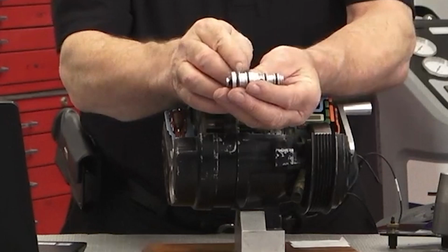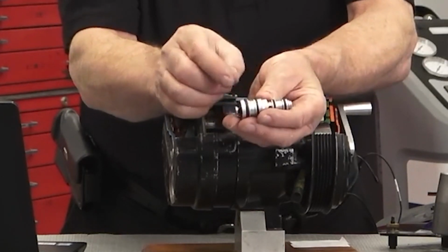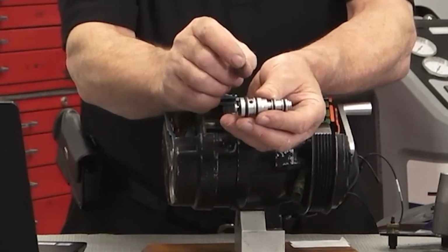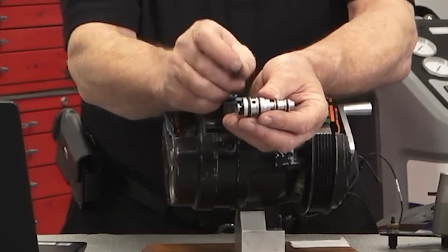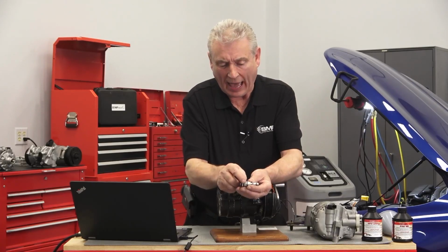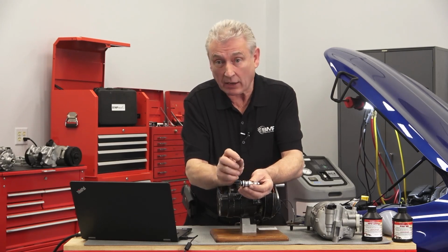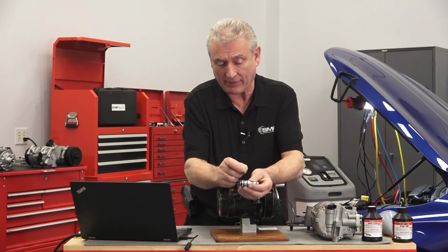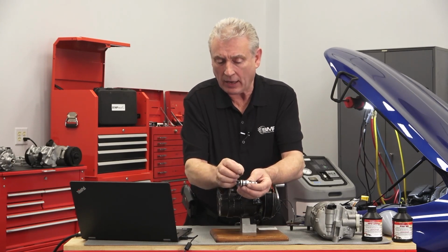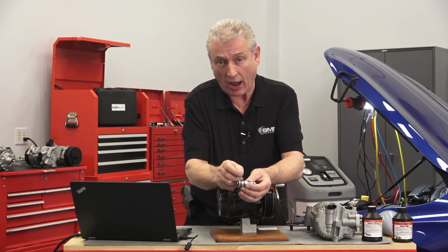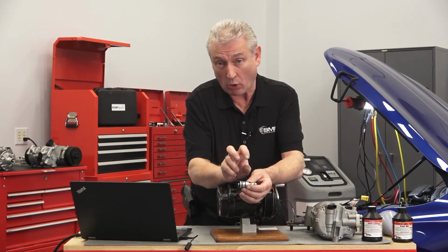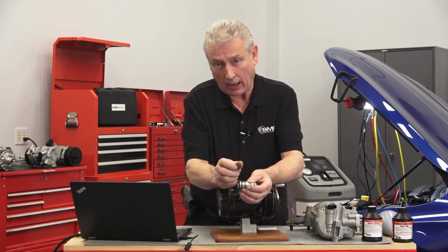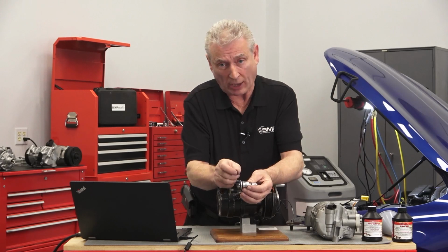There is a pneumatic bellows in here. Through the hole, if I look inside, there's a pressure-sensitive bellows. That area of the valve is exposed to low side pressure, evaporator pressure, in other words the pressure inside the evaporator or in the suction line. Low side pressure, of course, is a function of the heat load on the system. If I move the blower speed from low to high, that's going to put more heat load on the evaporator.